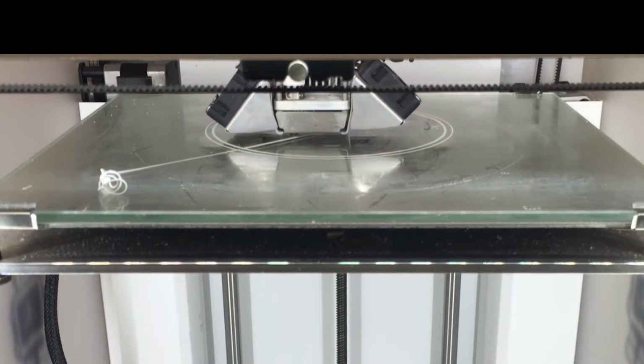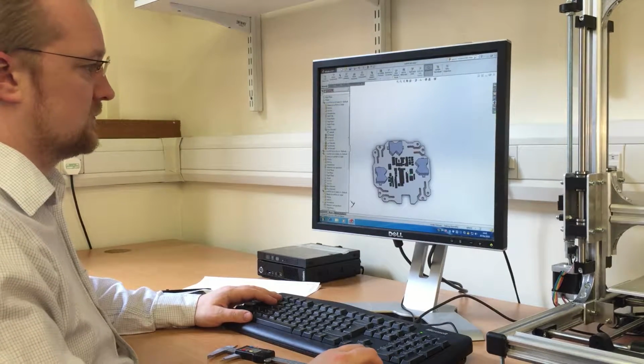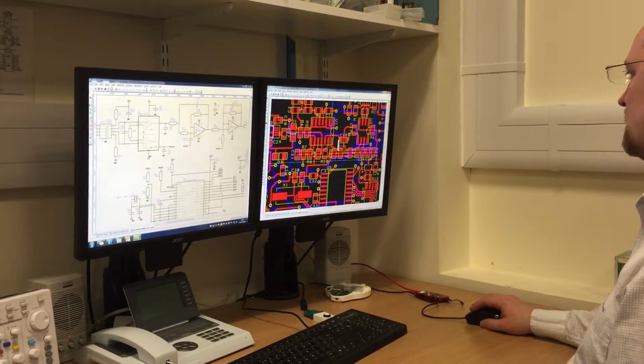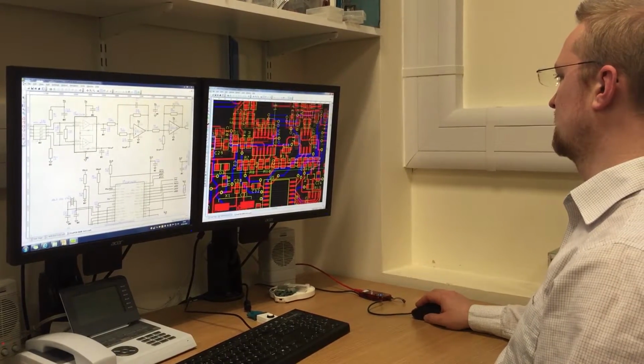The design of the Flow Taker is not immediately suited to manufacturing using 3D printing technologies. The printing time is over 24 hours and in fact the end result is unusable. A medical device intended for redistributed manufacturing needs to be designed differently. We have addressed every aspect of the design. We also needed to substantially redesign the electronics alongside the case.